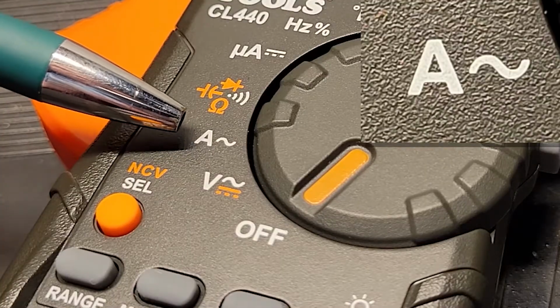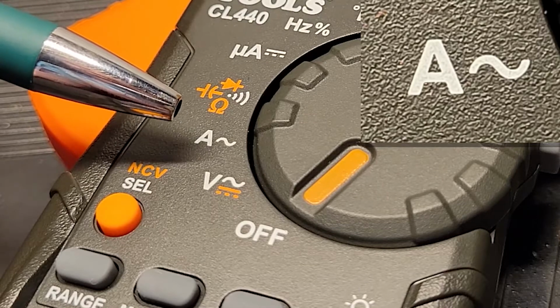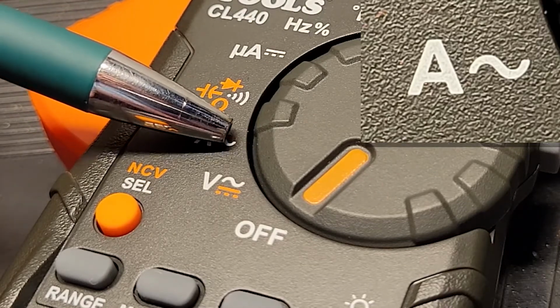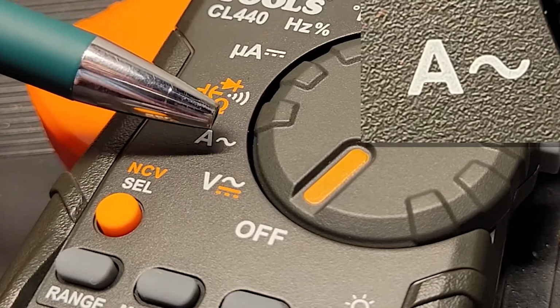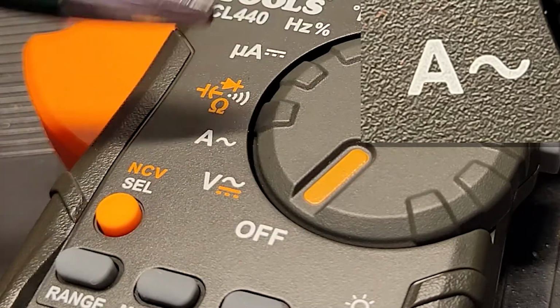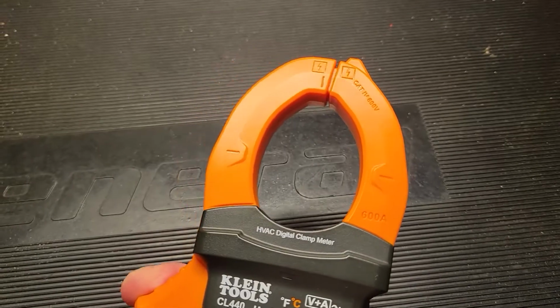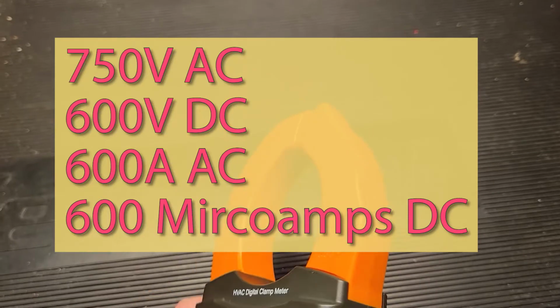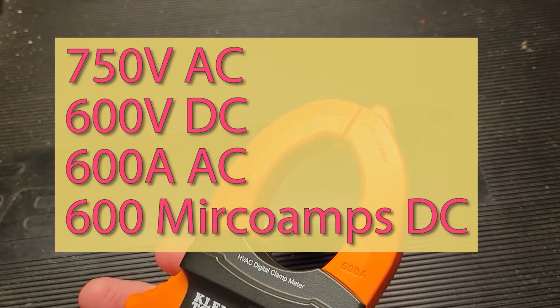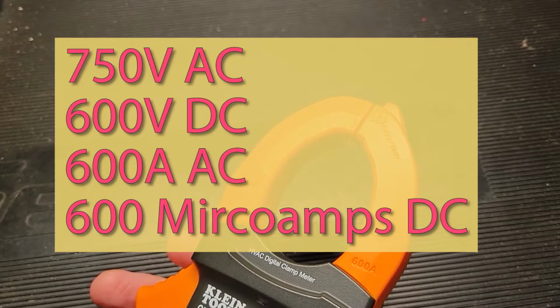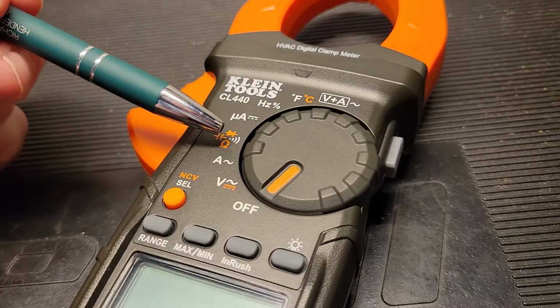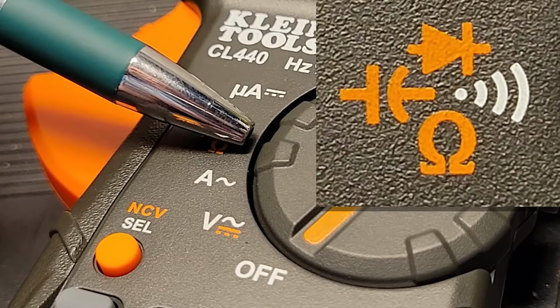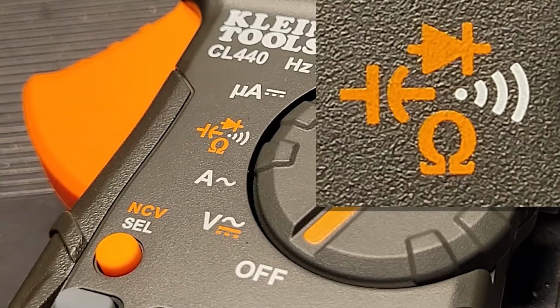Going to the next position, we have A, which is for amperage, and we only have the sine wave, so it's AC. This device cannot read DC amperage. Know that this digital clamp has a limit of 750 volts AC, 600 volts DC, 600 amps AC only, 600 microamps DC. Keep these limitations in mind when using this tool, and you should be safe. Going up from amps, we see a grouping of symbols. The one in white is continuity, which generates a tone on a closed circuit.